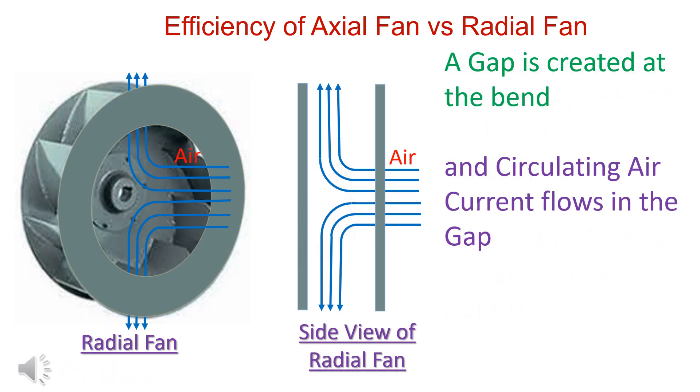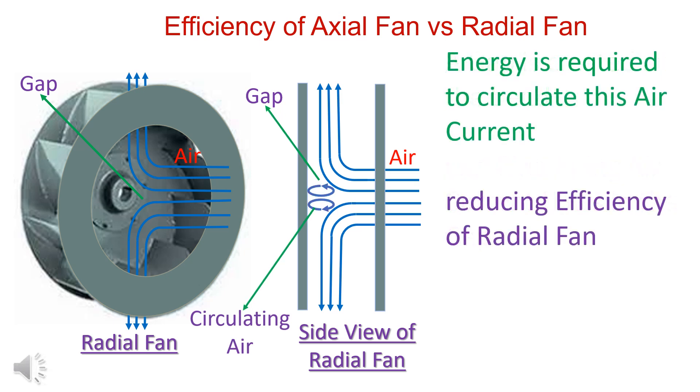In a radial fan, a gap is created at the bend and circulating air current flows in the gap. Energy is required to circulate the air current. This energy is lost, resulting in the reduced efficiency of radial fan.